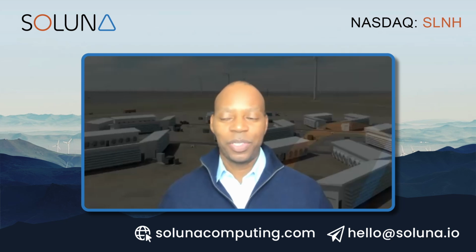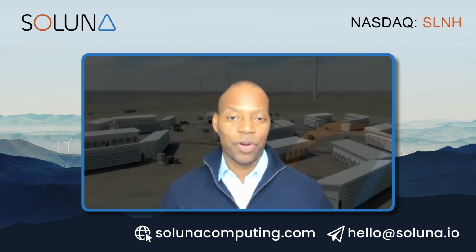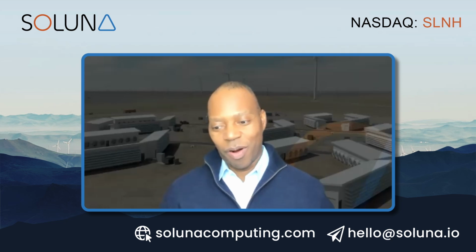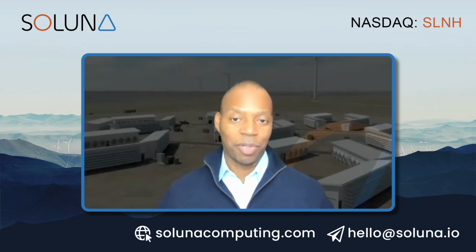Yeah, absolutely. We just put out this announcement recently that shared a study we've been working on for the past year around looking at the load profile of Dorothy, the shape of the power in that region, and the carbon footprint of our facility relative to other data centers in the ERCOT market. I'm really excited and proud to say that our facilities and our design, our approach to putting the facility behind the meter, focused on eating wasted or curtailed energy, has created a solution for renewables. But it's also proven that you can build data centers that are less carbon intensive for applications like Bitcoin and other applications, especially as it relates to AI.